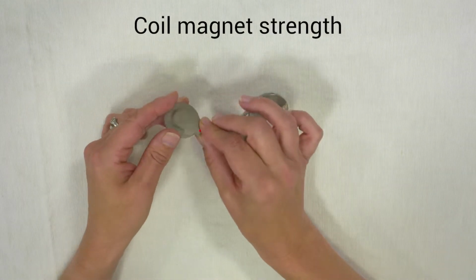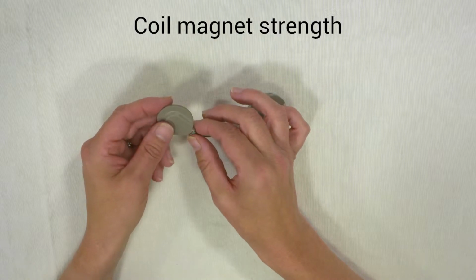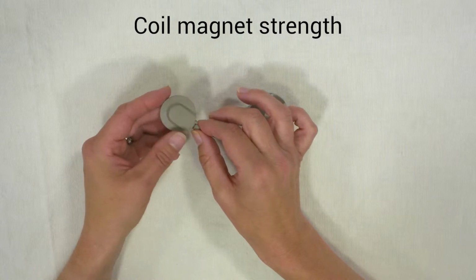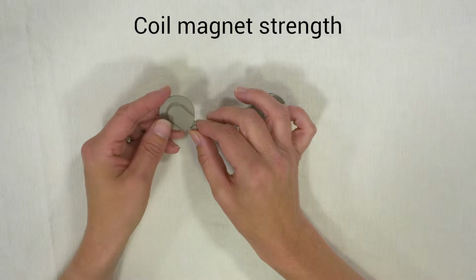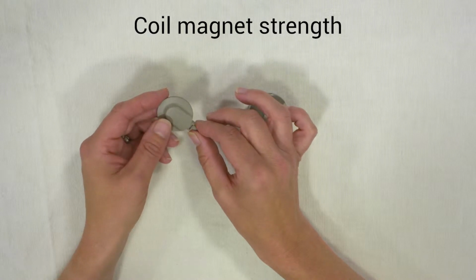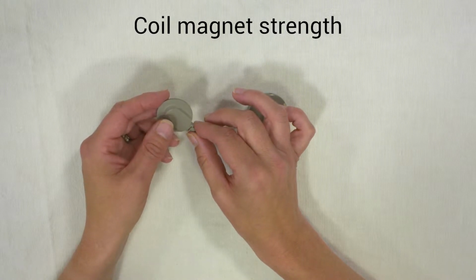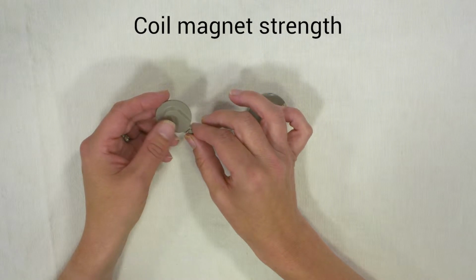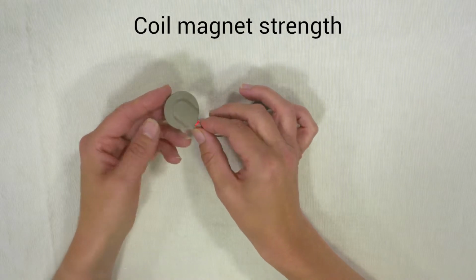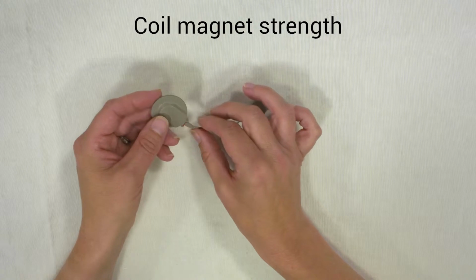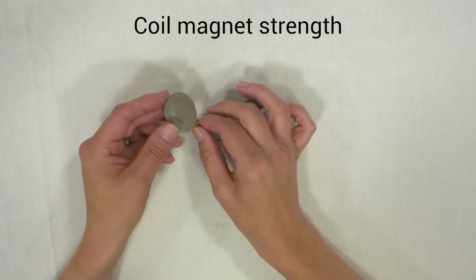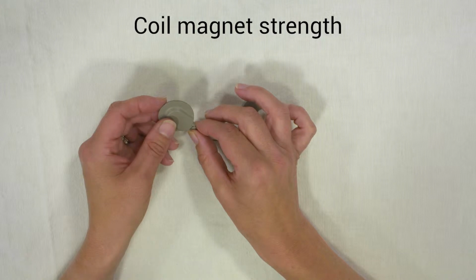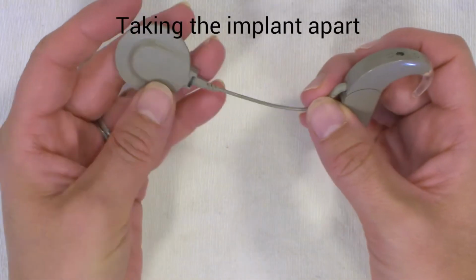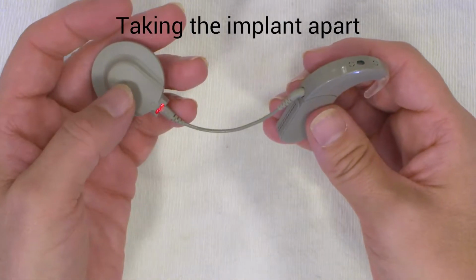The audiologist will choose which strength the magnet needs to be, and they'll regularly check it because it's really important to get the magnet strength right. Too tight and you could damage the skin around your implant. Too weak and it will keep falling off. So it's really important to keep an eye on it and mention if you get any redness or soreness around the magnet site. The coil and lead can be removed from the processor.